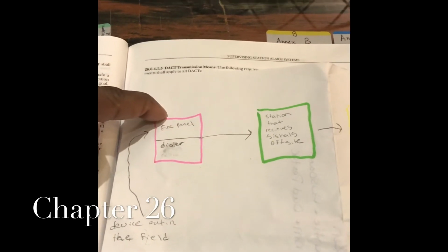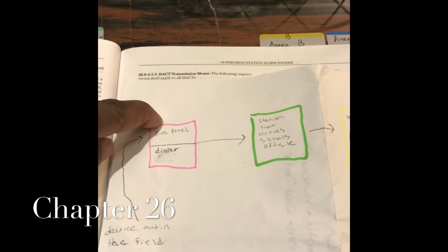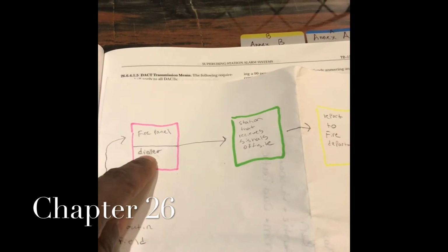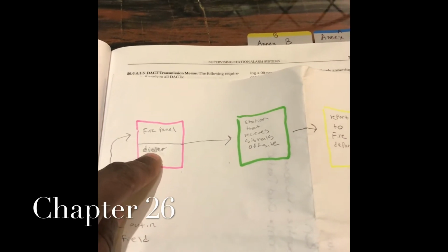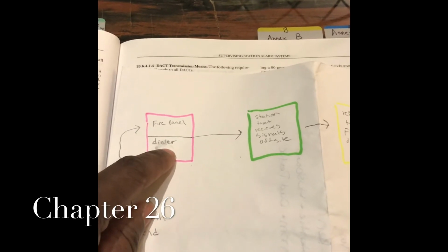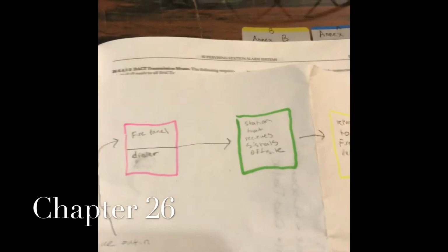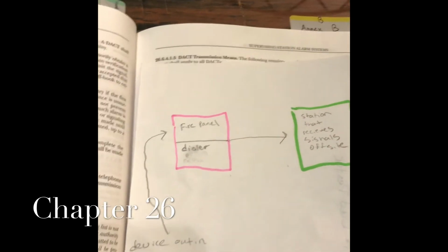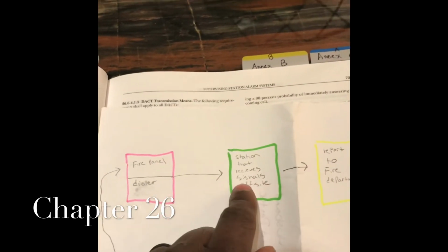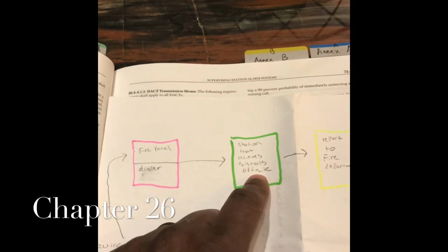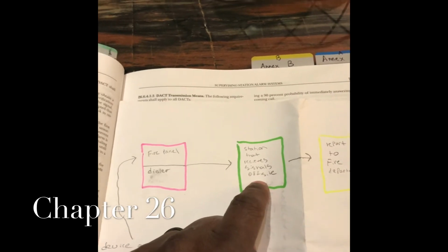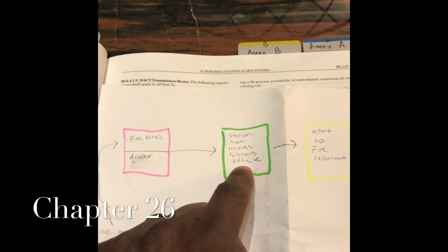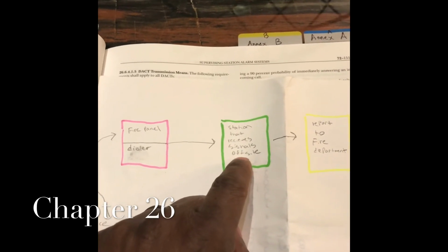From your fire alarm panel, it does all the reporting and it goes through the dialer. From the dialer, it dials out. The dialer is either going to be a hard line, IP line, or a radio. Most hard lines are going away. It's very few jurisdictions now that still have copper lines. Most things are going to IP or radio. So from the dialer, it goes to either a central station, which receives the signals. It's either going to go to a proprietary station, which is a building or company that monitors their own signal, or it's going to go to a remote station, which is the same as a central station with less requirements.